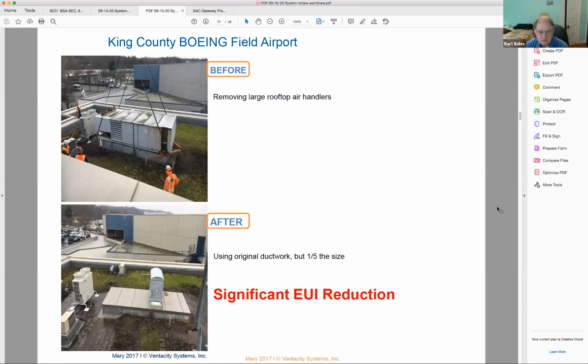So look at what we're talking about doing. Here on the top is a rooftop air handler, and we're thinking about replacing it with what's in the lower picture. So the item on the left is a heat pump condenser. The item on the right, if you could point at them, Henry, it'd be great. Bottom picture. The item at the right is the heat recovery ventilation unit. The item on the left is the heat pump condenser unit. Next slide.